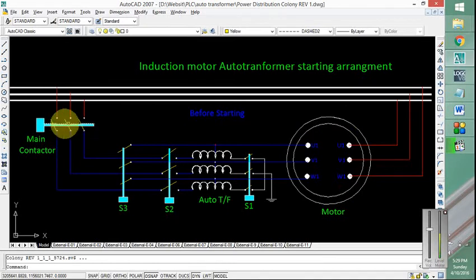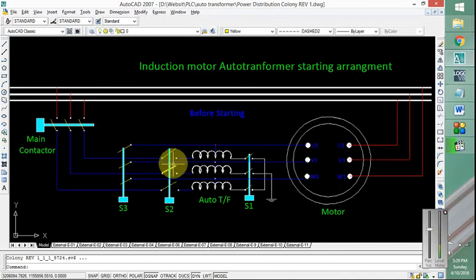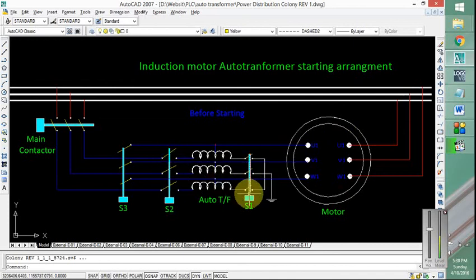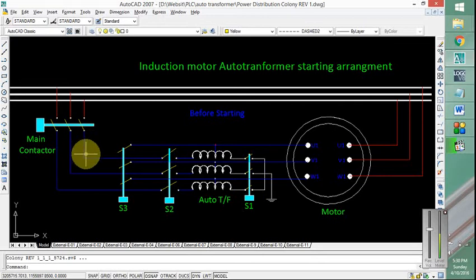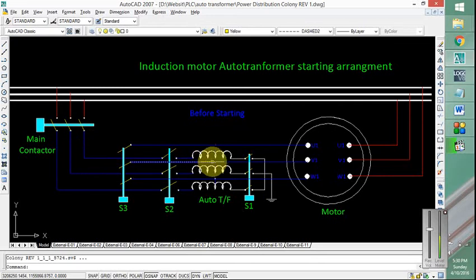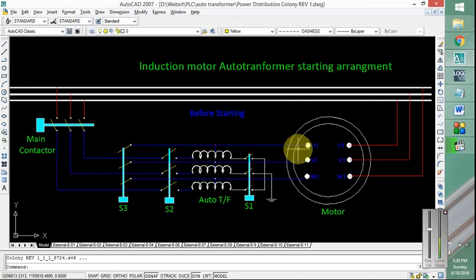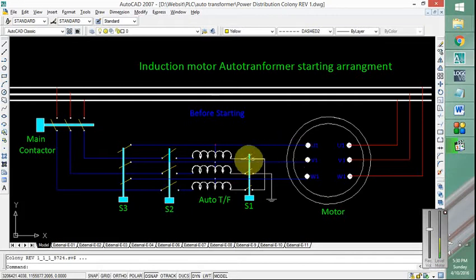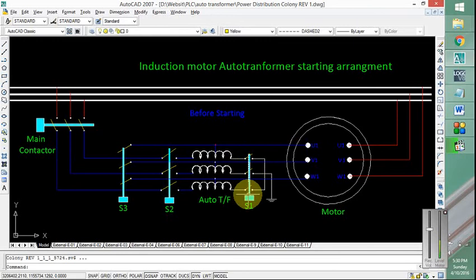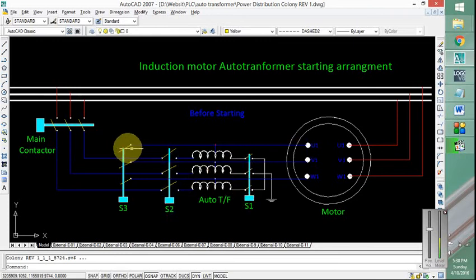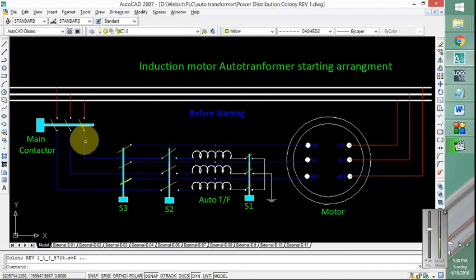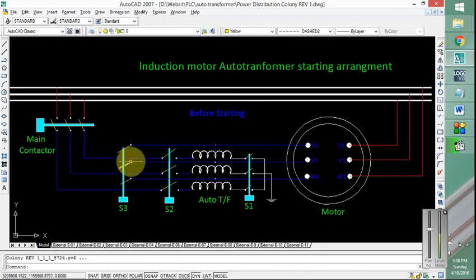Initially this contactor will be closed along with this contactor and this contactor. So the current will follow the path through the auto transformer then into the motor windings, giving it reduced voltage. But when the motor gains enough speed, this contactor is opened while this one is closed.